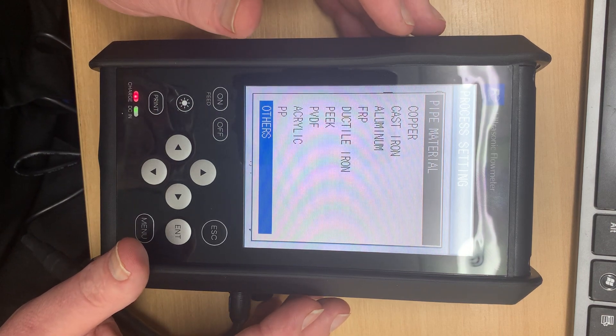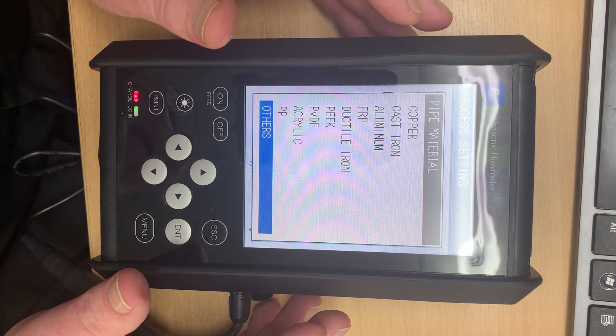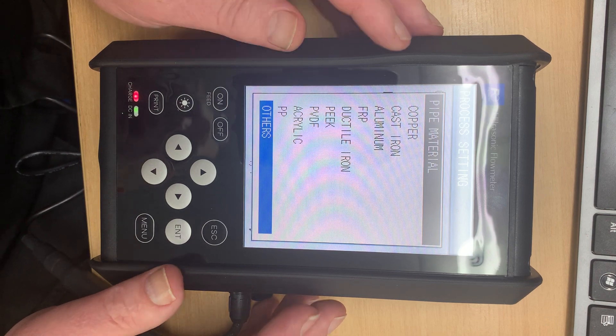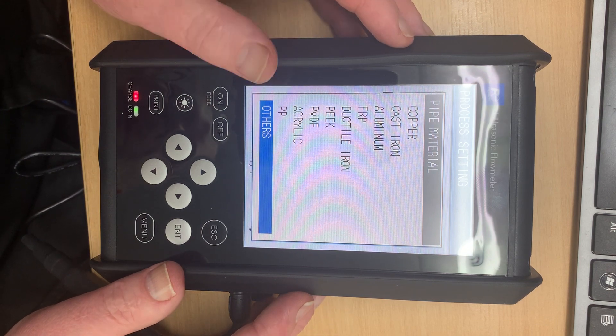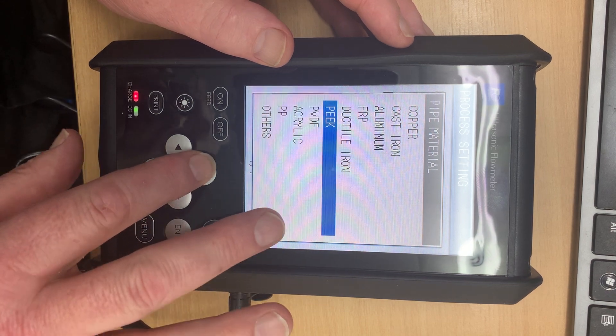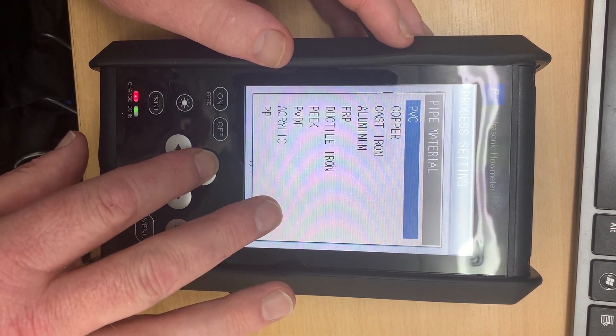But if you have a pipe that is not on this list, all one needs to do is find out the sound speed through that material and you can enter a sound speed there. But let's say for now we're in a food situation so we're going to have stainless steel.